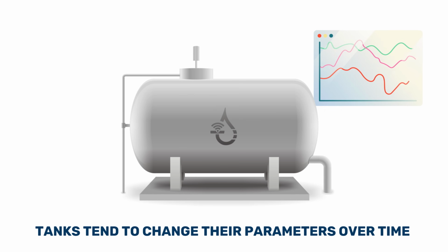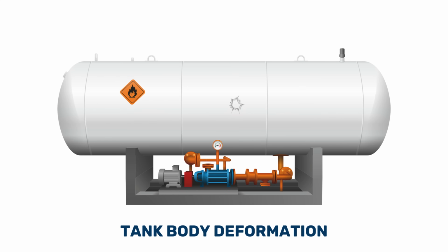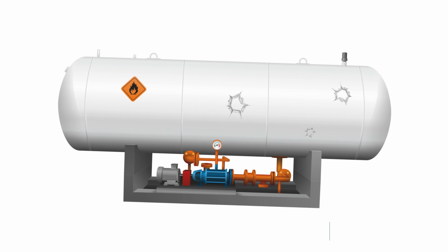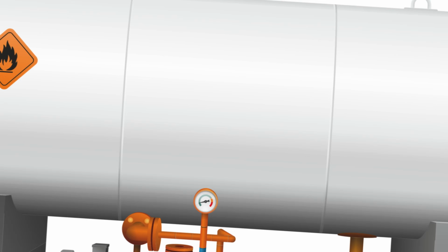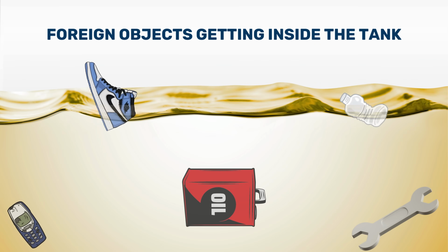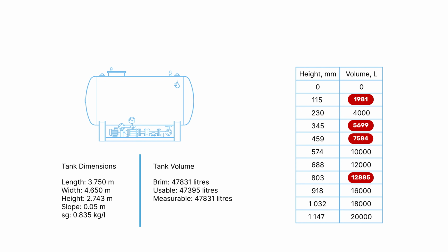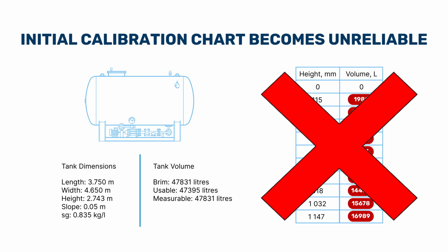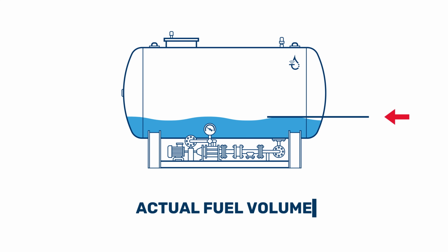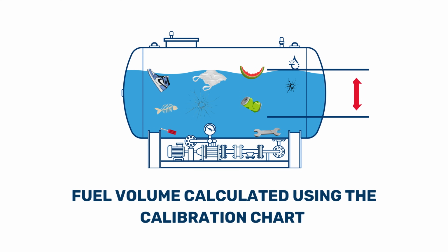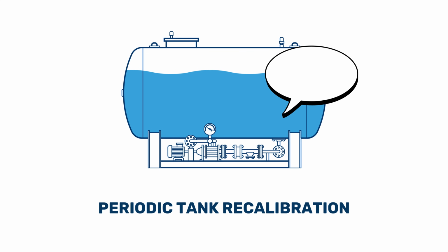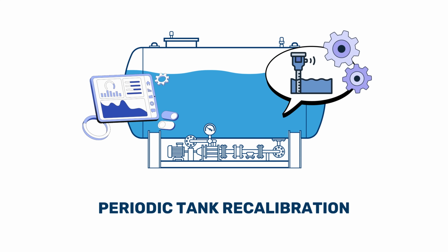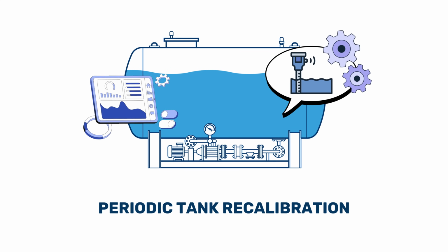During operation, tanks tend to change their parameters due to various types of deformations and external influences. This may be tank body deformation, tilt, foreign objects getting inside. Therefore, during operation, the initial calibration chart of the tank becomes less and less reliable. The discrepancy between the actual fuel volumes and the volumes calculated using the calibration chart provided by the manufacturer results in the loss of a true accounting of the petroleum products. It leads to a necessity to periodically provide tank recalibration in order to create a new actual calibration chart, which matches the present tank state.